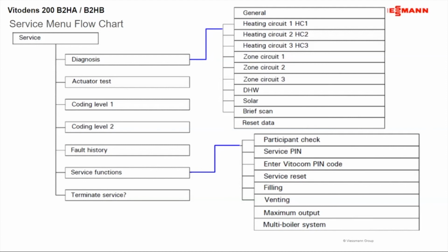Venting is what I call, or what we call here, purge mode. What I normally do is I put it in that mode, and then on the left-hand side, I have an isolation valve underneath that boiler drain that we give you. I shut that, then just open up the boiler drain with a hose and purge out the rest of the air in the system. It works really well.